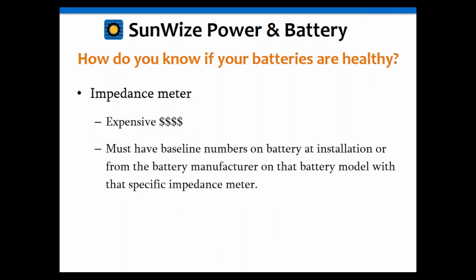Okay, the other way to know if your batteries are healthy or not is with an impedance meter. These things are very expensive, I mean, on the order of thousands of dollars. They range anywhere from like $1,000 to $5,000, depending upon the meter. So they're not cheap. Not only expensive, they can only be used in certain circumstances.